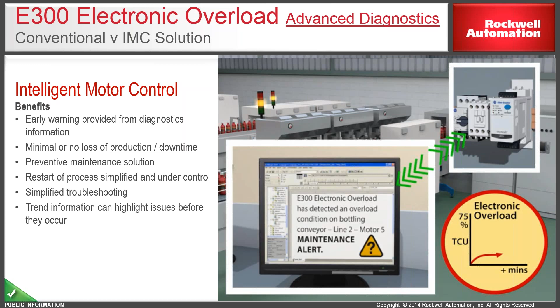And you don't have to restart the complete motor, which will help you reduce motor cost. The troubleshooting is very simplified because you are aware where exactly the fault is occurring, and if there is any failure of the relay, you can just directly replace it. So these are some benefits. In the case of a thermal overload relay, it will just indicate on or off, or trip. In the case of an electronic overload relay, it is going to profile the built-in thermal capacity utilization of the motor when it reaches the overload condition, and the next time it is going to happen, it will pre-alarm you about the motor overload condition, so you can take proactive actions.